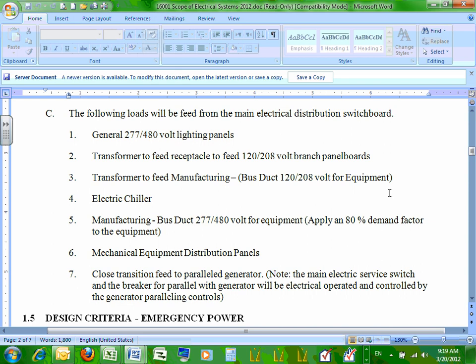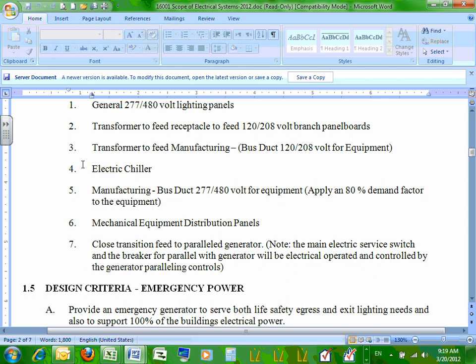We're looking at feeding bus duct when I need the 120/208 equipment, and much of the equipment is 120/208. So I'm looking at providing a 120/208-volt system with its own transformer from my service to feed that equipment. And so that transformer, like these other items I've talked about, would be loads that I'm expecting to feed directly from that main electrical distribution switchboard. Electric chiller, we expect to go right to the switchboard. And then I'm looking at some 277/480-volt bus duct that again would supply the 480-volt equipment within that space.